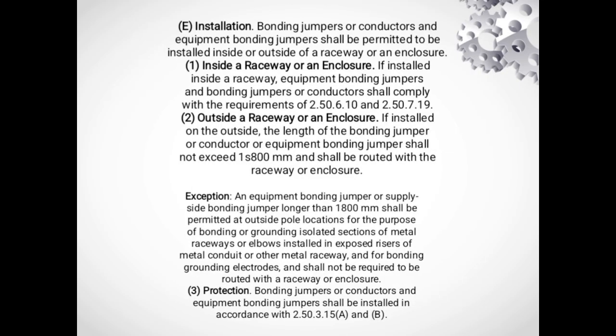Installation: bonding jumpers or conductors and equipment bonding jumpers shall be permitted to be installed inside or outside of a raceway or an enclosure. Number 1, inside a raceway or an enclosure: if installed inside a raceway, the equipment bonding jumper and the bonding jumpers or conductors shall comply with the requirements of 2.50.6.10 and 2.50.7.19. Number 2, outside a raceway or an enclosure: if installed on the outside, the length of the bonding jumper or conductor or equipment bonding jumper shall not exceed 1,800 mm and shall be routed with the raceway or enclosure.